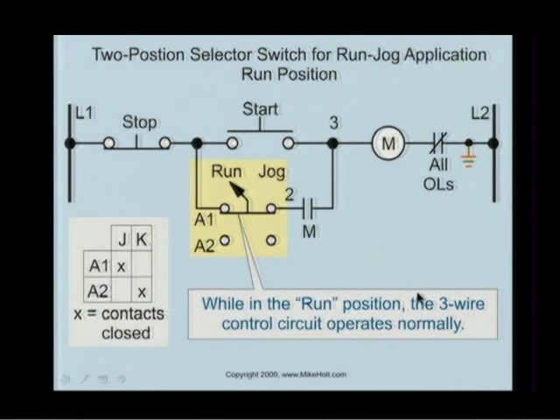Let's put this together in an actual circuit. I love our 3-wire control circuit now. I feel comfortable. I'm not as tired as I was yesterday with them. All right. Let's say we are in the J position, and in the J position, it indicates that A1 is closed. We can visualize that. So if I press the start button, I energize the M coil, which closes the M contacts, which then is going to lock the M coil in. Main contacts close. The overloads are not open. The motor runs. The main contacts are not being shown. Everybody with me there? So now, how do you stop this?